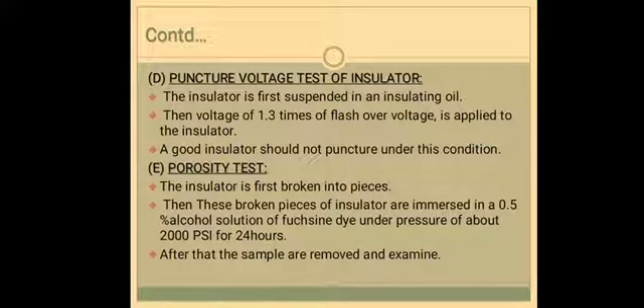Next is the porosity test. The insulator is broken and immersed in a 0.5 percent alcohol solution which will be under a pressure of 13,800 kN per meter square. The duration will be for 24 hours. The broken insulator will then be taken out and broken again — it should not show any sign of impregnation.